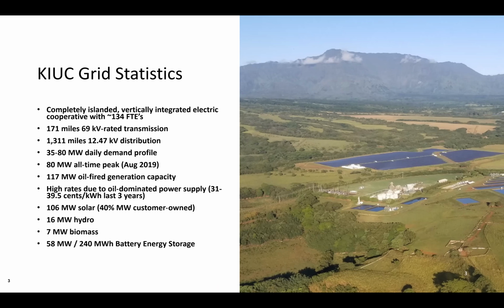We do transmit. Our transmission voltage is, you might consider it sub-transmission. It's 171 miles and roughly about 1,300 miles of 12.47 kV distribution. And our loads have been fluctuating between 35 megawatts and 80 megawatts, which is an all-time peak back in August of 2019, pre-COVID levels. We do have 117 megawatts of oil-fired generation capacity, and we traditionally have had high rates for our members, which is really the driver for us to go renewable when we get to the future slides. So our rates have been fluctuating anywhere between 31 and 39.5 cents a kilowatt hour over the last 3 years for an average residential member.